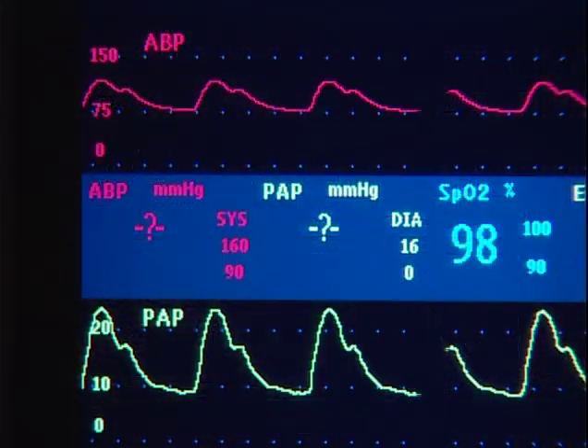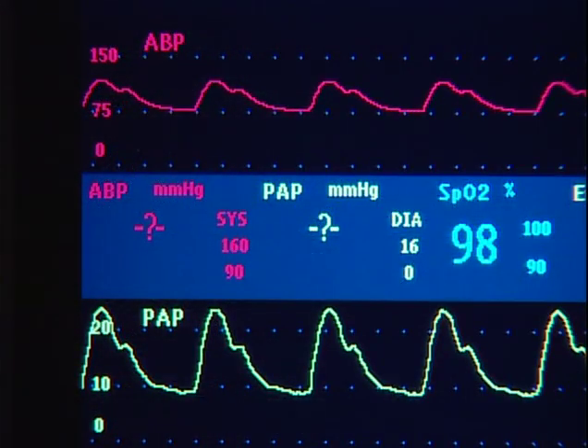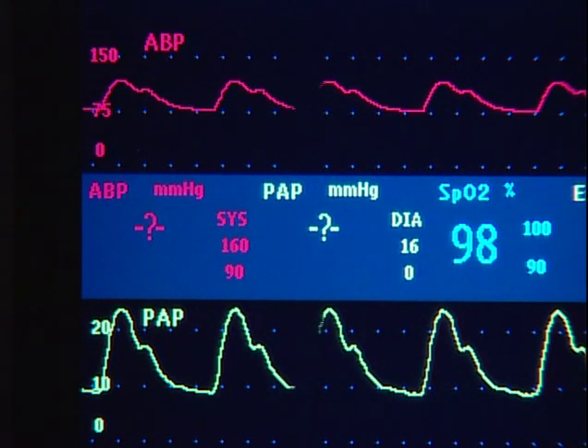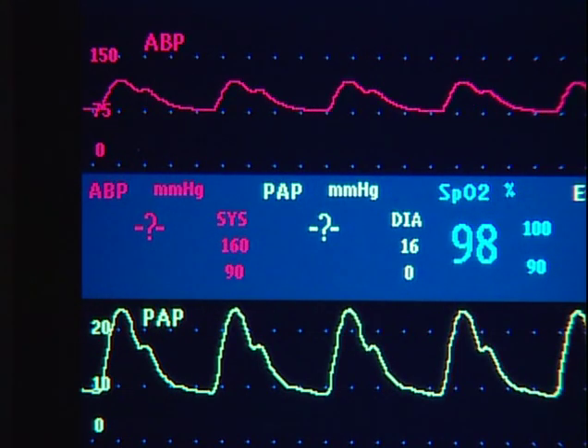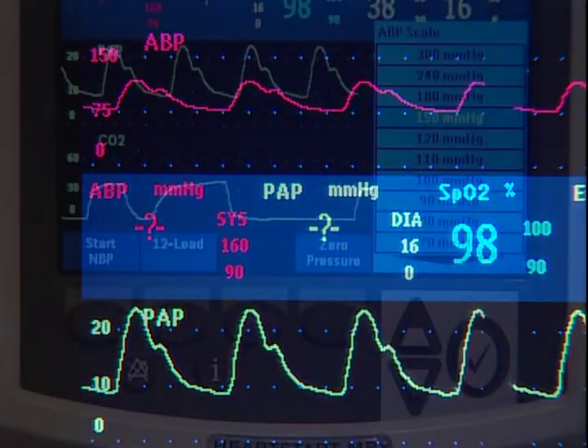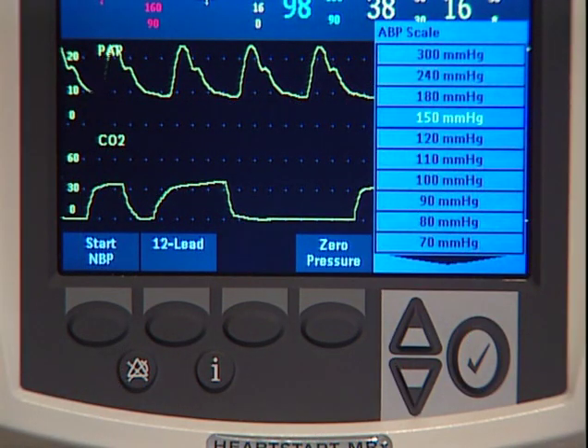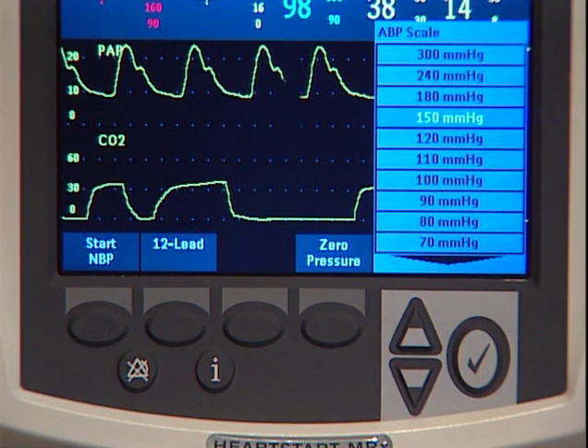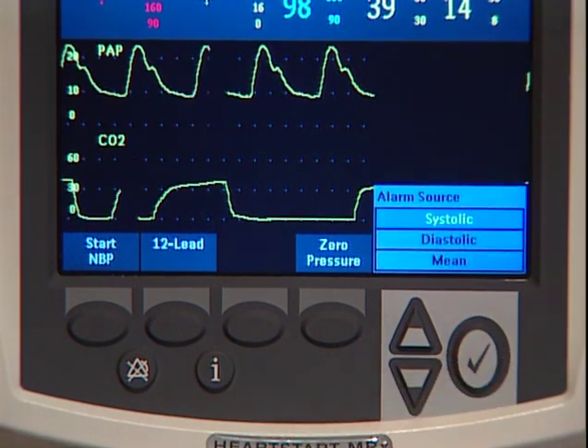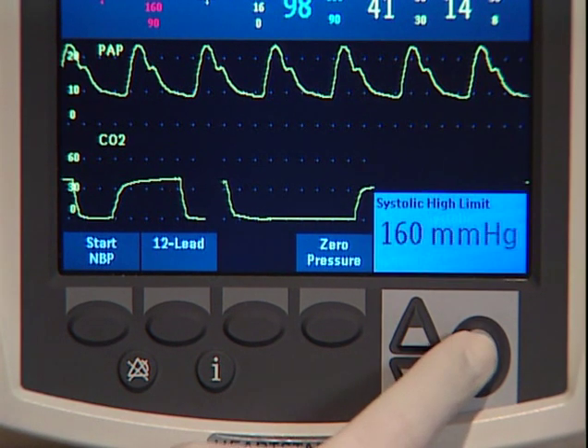The label is a unique identifier for each pressure type. When you choose a label, the Heartstart MRx uses that label's configured color, wave scale, and alarm settings. After selecting the label, these controls allow you to confirm or adjust the related wave scale, alarm source, and alarm limits.